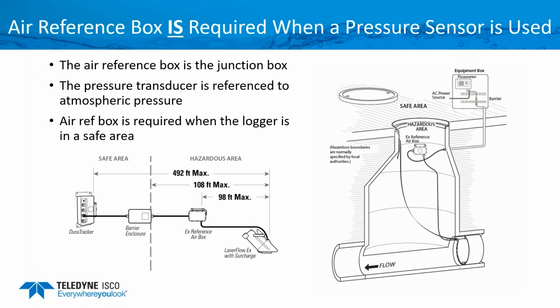Now, the other reason why you need the air reference box is in this location, we have the area velocity sensor down at the bottom. We're going to vent into the hazardous area, the classified area, go through a sealed conduit, and then on up to the controller. That controller could either be a logger, like the DuraTracker, or a signature meter. And so we do need to reference atmospheric pressure within the sewer to give us an accurate level reading.